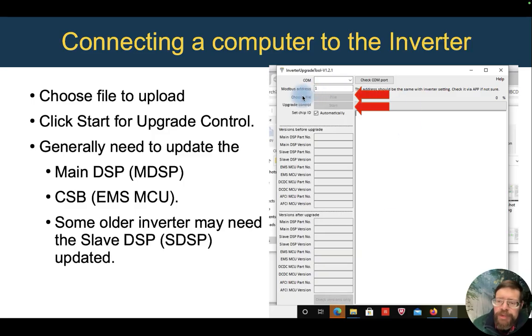Then you'll want to go to this one that says choose file, and that'll let you choose the file on the hard drive. Again, grab those files for the firmware updates off of the shared drive. And then hit start for upgrade control, and it will update the file. Make sure you keep this checked automatically here, because that means that it automatically checks and sends that file to the right processor in there. If you set that to manual, it can get all confused and be difficult to get figured out. So make sure that stays checked automatically so it sends the file to the right processor.